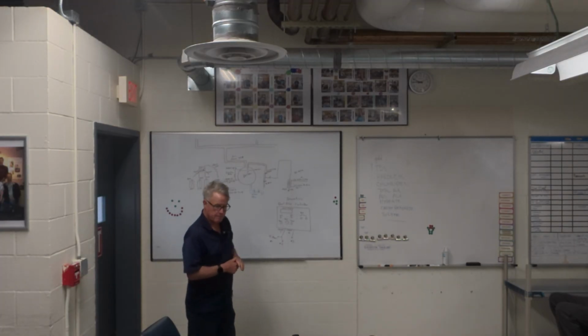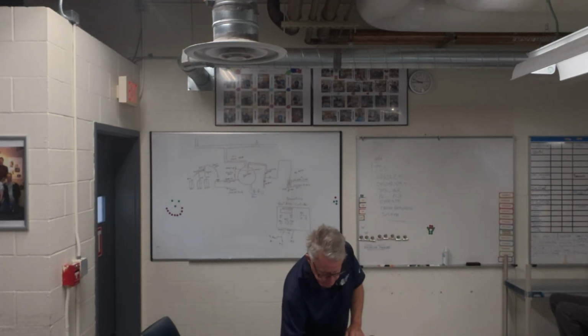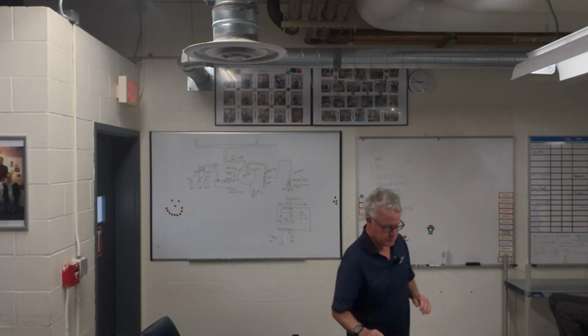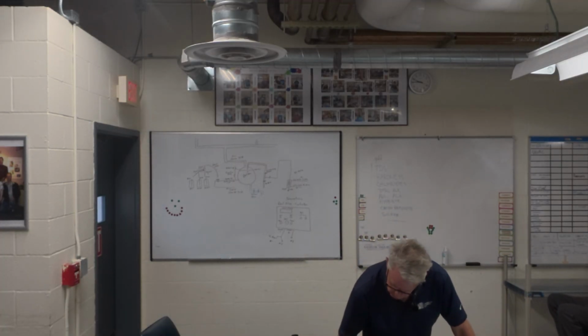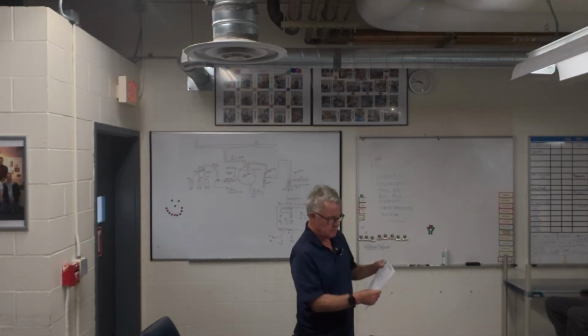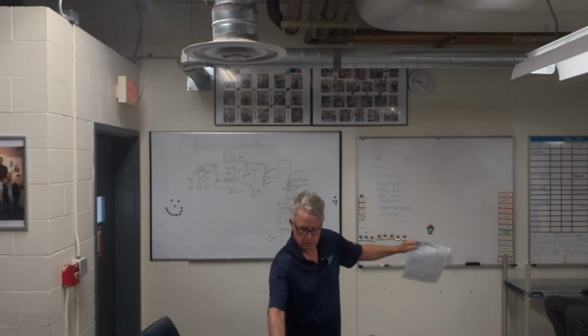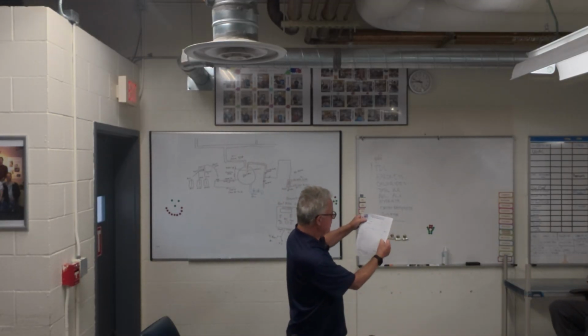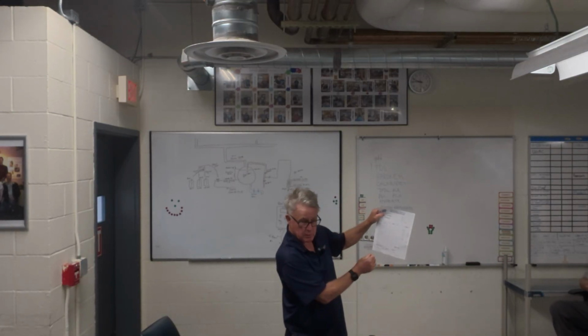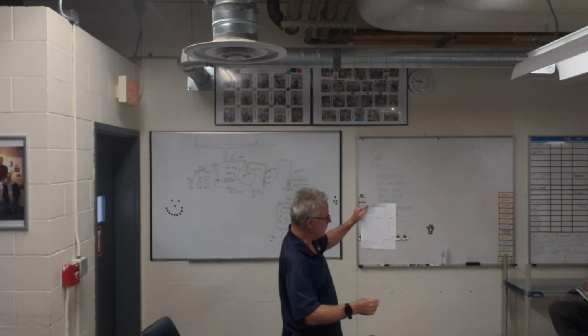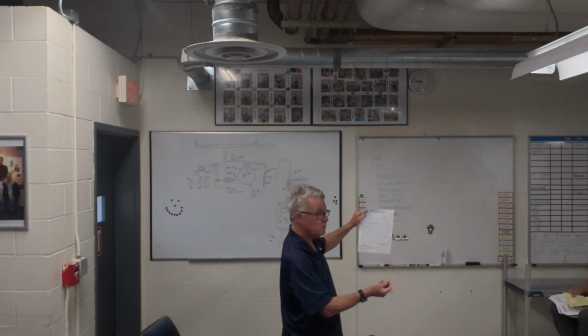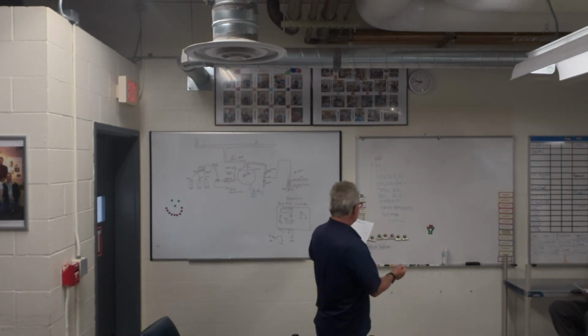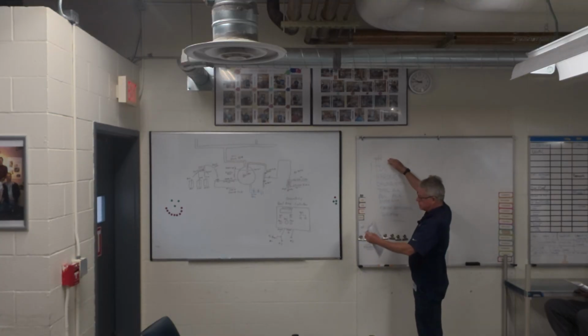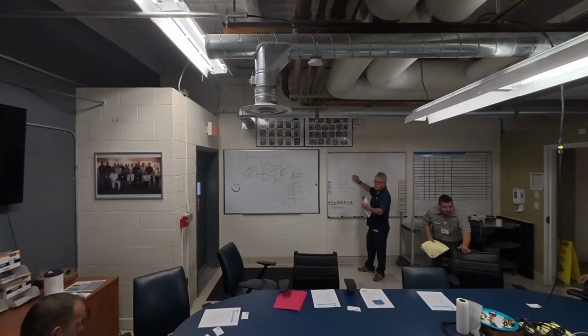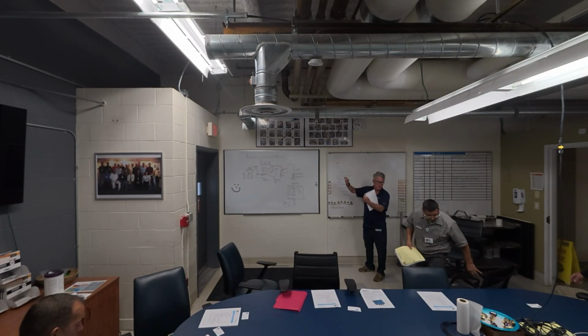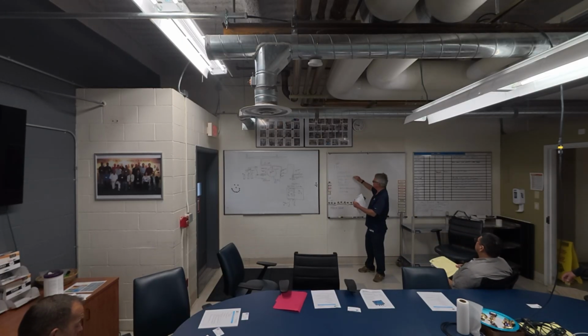As another advantage of our treatment program, we come by once a week and you'll see these reports online. These are the target areas we're trying to keep these boilers within. We'll leave a written report on site, which then goes back and gets put into a digital format. The main things we're looking at are pH within a certain range, and TDS, which tells us how well you're blowing down the boiler -- or whether the surface blow needs to be adjusted.